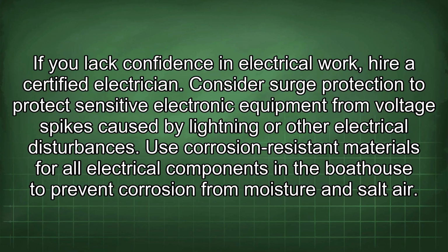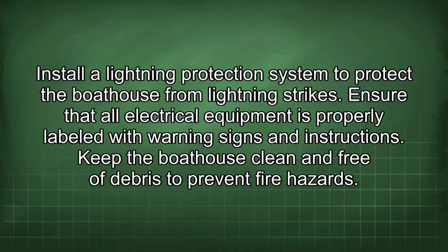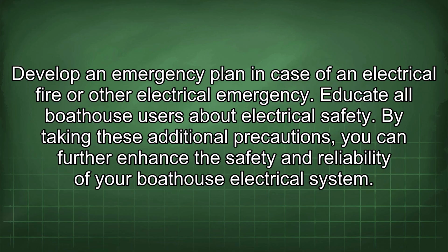Consider surge protection to protect sensitive electronic equipment from voltage spikes caused by lightning or other electrical disturbances. Use corrosion-resistant materials for all electrical components in the boathouse to prevent corrosion from moisture and salt air. Install a lightning protection system to protect the boathouse from lightning strikes. Ensure that all electrical equipment is properly labeled with warning signs and instructions. Keep the boathouse clean and free of debris to prevent fire hazards. Develop an emergency plan in case of an electrical fire or other electrical emergency. Educate all boathouse users about electrical safety. By taking these additional precautions, you can further enhance the safety and reliability of your boathouse electrical system.